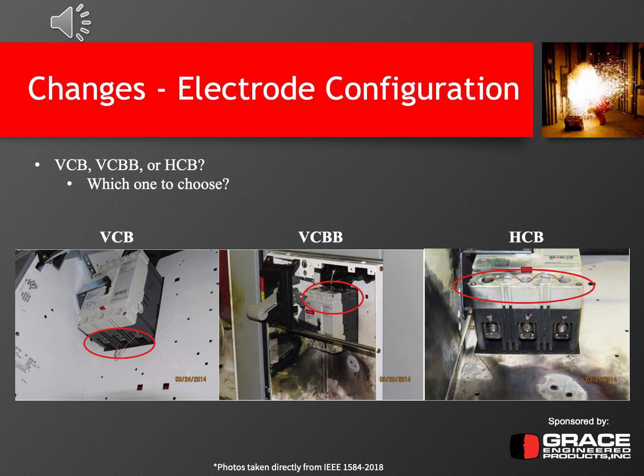Here's another example of a single installation that may have multiple different types of electrode configurations, which again makes things a little more confusing. The photograph on the left shows a VCB configuration, and it's basically the load conductors exiting the circuit breaker. The middle photograph is a VCBB electrode configuration, as the cables enter the top of the breaker, and you have the top of that breaker as an insulating barrier. And then on the right photograph, there are screw terminals at the connection points. You can screw in the cables that connect to the bottom of the breaker, and because those screws are live and exposed, touching the live energized cable, that would also be an HCB configuration.